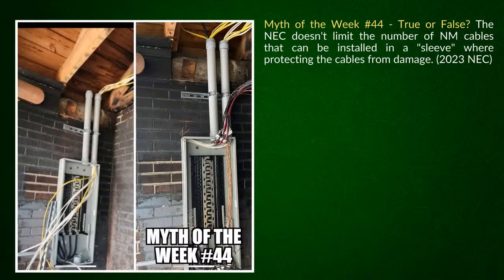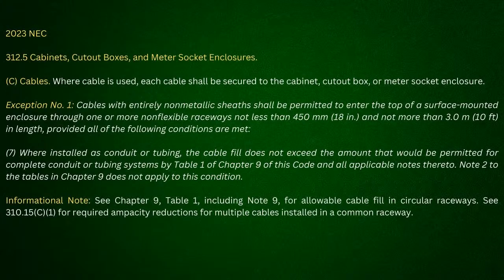I don't remember the code where they actually allowed you to do this installation. I just didn't have time to go back and look at it, where they would go through the top plate and have a 2-inch going up and then running the non-metallic sheathed cable down through there. Right. That was in the code a while back, and then they took it out because they did other things in the code so they didn't have to be specific about that, because it was nothing more than a sleeve. Okay, right. I will try next week to find that, because we actually had it in our book with an illustration on it.